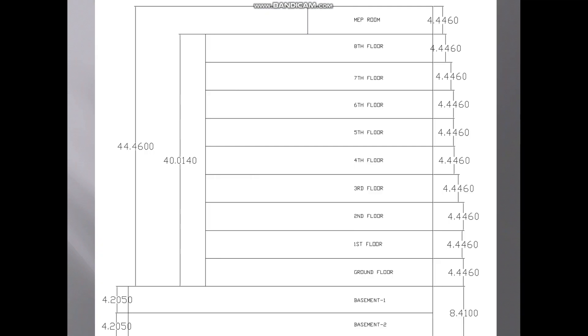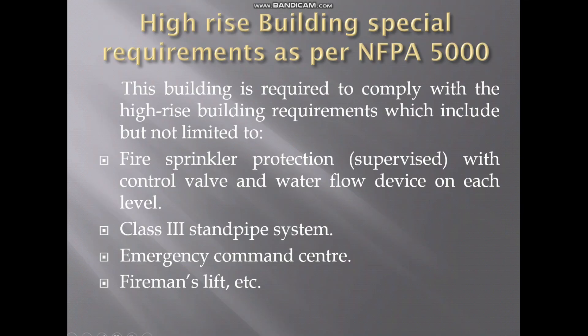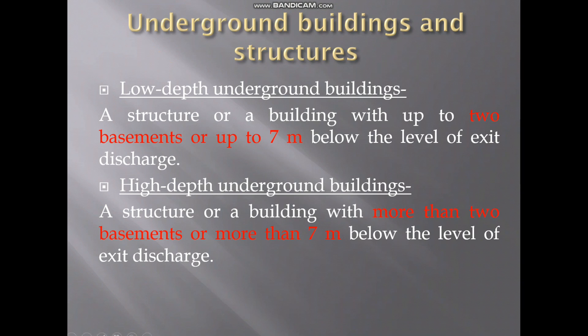In our example, we have two basements — basement one and basement two — with a total depth of 8.4 meters, each at 4.2 meters. A structure with up to two basements or up to seven meters below the exit discharge level is considered low depth. In our case, while we comply with the two-basement rule, the depth is more than seven meters, so it will be categorized as a high-depth underground building.